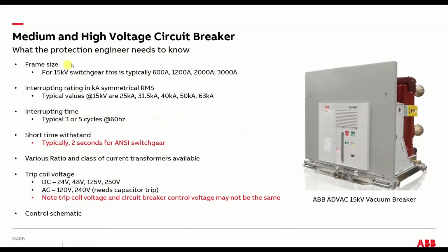all, plug and play. If you're a protection engineer, the basics you need to know are the frame size. And this is pretty typical frame sizes, 600 to 3,000 for 15 kV class gear. That's it. So if you needed a 100 amp breaker, for 100 amp application, the smallest you can get is a 600. And actually, in medium voltage gear, we bought them out of 1,200. So if it's a 100 or a 200 amp breaker, you're in a 1,200 amp frame. And all the actual where it trips at is set by the CT. And the relay. The interrupting values are good to know.